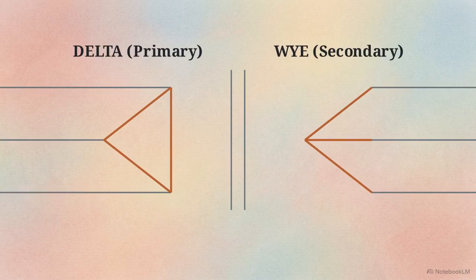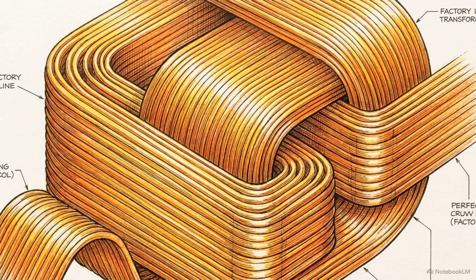This schematic illustrates a delta-Y winding geometry. Engineers use this triangular loop to trap rogue zero-sequence currents. The triplens circulate within this loop, neutralizing themselves as heat, preventing them from traveling upstream into the grid. By simply manipulating the physical shape of copper wire, engineers can correct a mathematical corruption of the power supply.